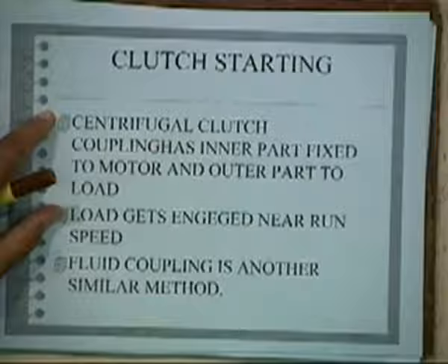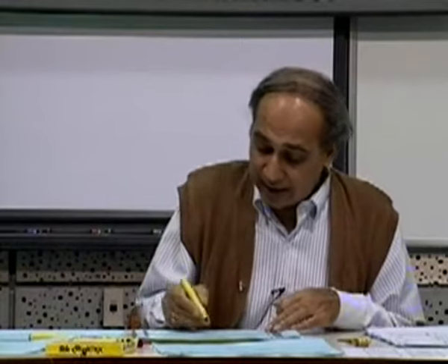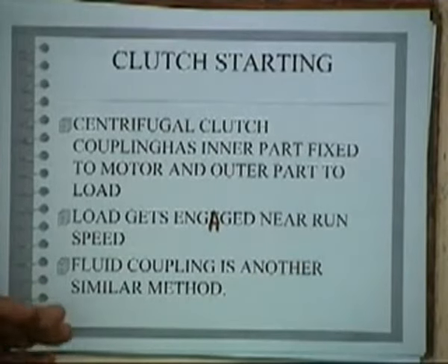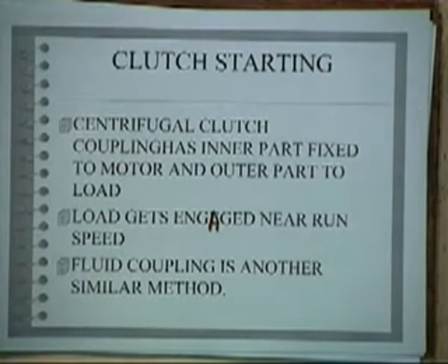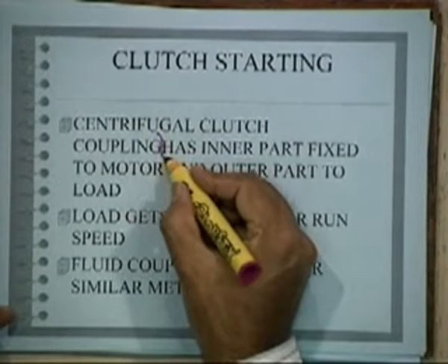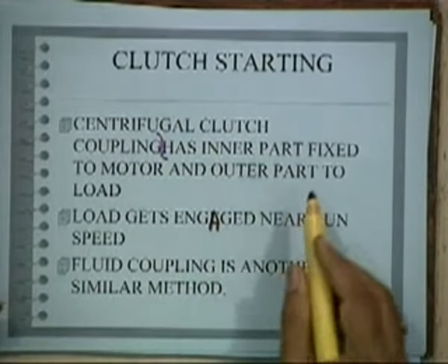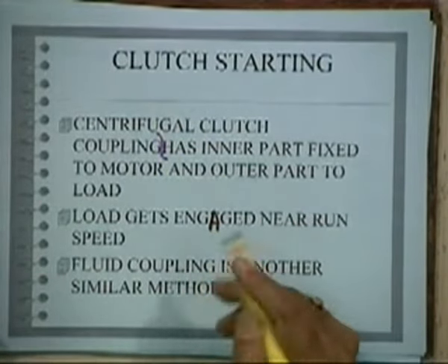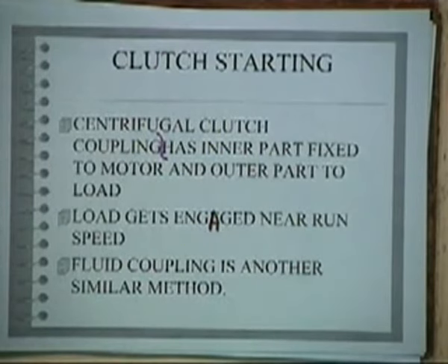This way you are able to reduce the starting needs. The load comes on after the motor has reached the requisite speed. Therefore, the load gets engaged near run speed. This is the main criterion that you will use here. So the clutch coupling has a method to engage or disengage depending upon the speed.